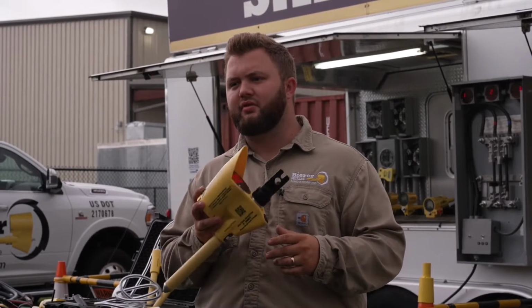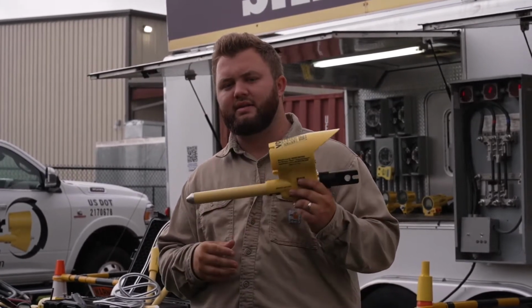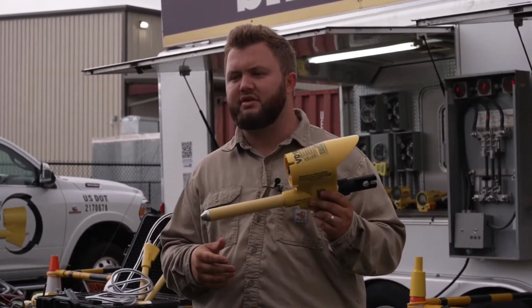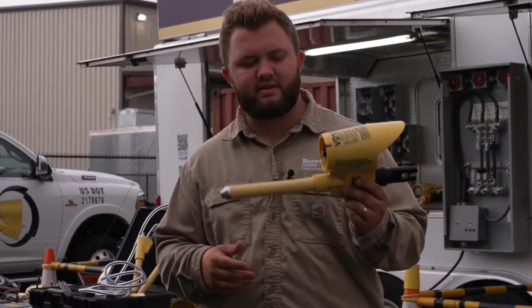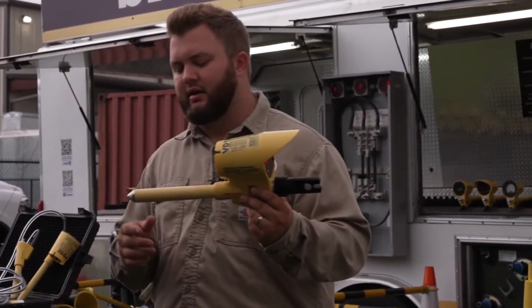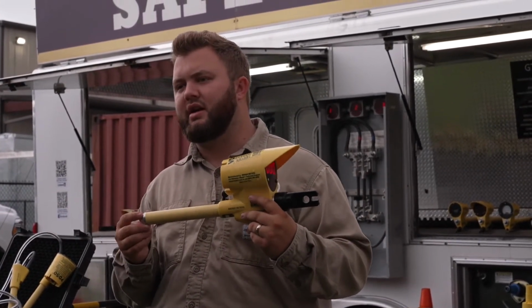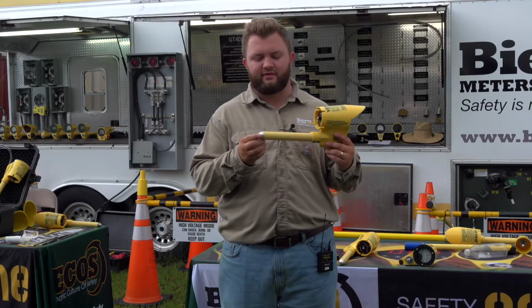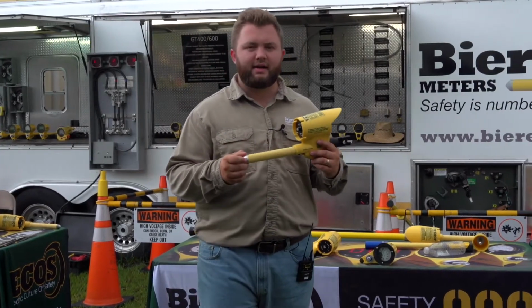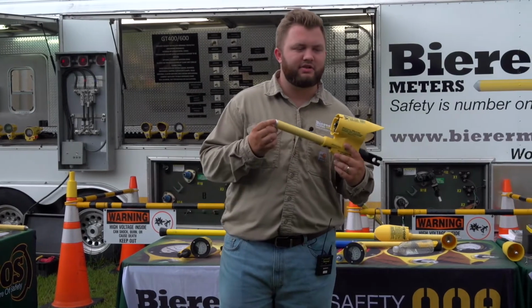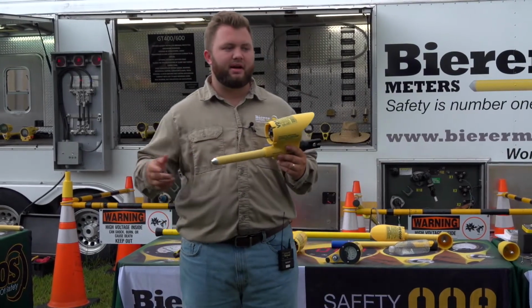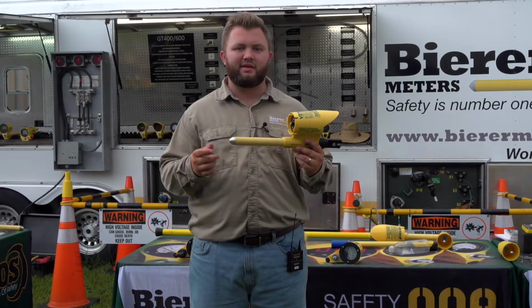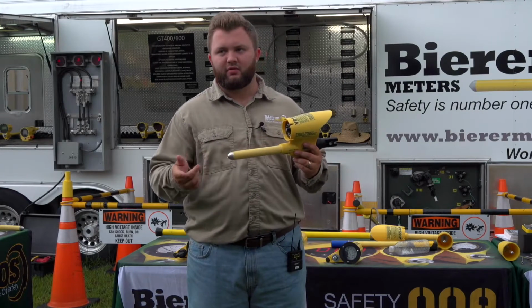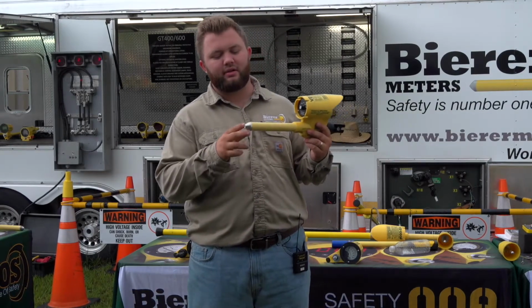Next, I'll go into the tool functionality, how any manufacturer's voltage detector or voltage indicator works. First, you always want to make sure you're using a direct contact device. If you're not using a direct contact device, the tools can be affected by other potentials nearby. They're not going to give you as good of information. We always recommend using a direct contact tool.